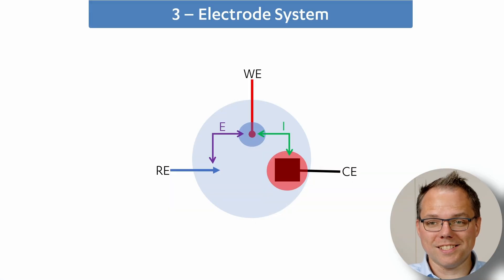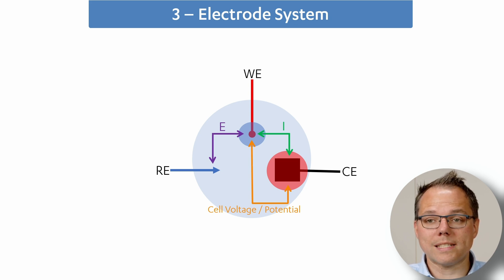There's one thing that many people don't pay attention to or are not constantly aware of: there is a potential between the working electrode and the counter electrode to drive exactly that current. That potential is adjusted so the current can flow that will guarantee the potential between the working and reference electrode. That potential that we apply between the counter and working electrode is the cell voltage or cell potential.